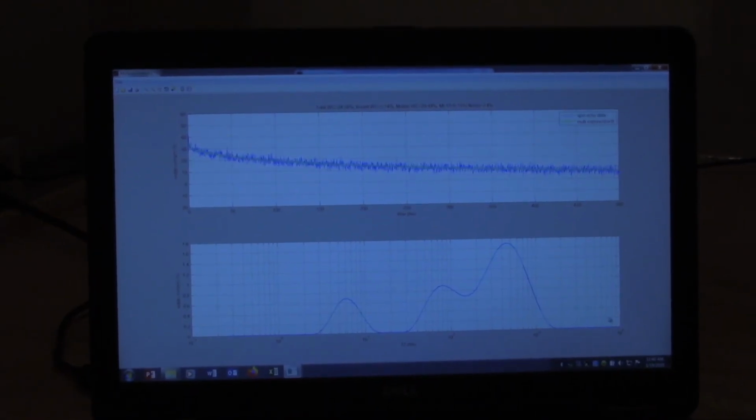So here I just wanted to show the difference of the results if you use more stacks. In this case, we have 34% water content, which is pretty similar, but our noise level has gone down to 2.4%. I used 40 stacks for this one, and we were able to reduce our noise down to 2.4% from 3.4. You can also see that because we have higher quality data now, we were able to resolve a slightly different relaxation distribution. We still have this trimodal distribution, but we have removed that noise at the really long relaxation times.